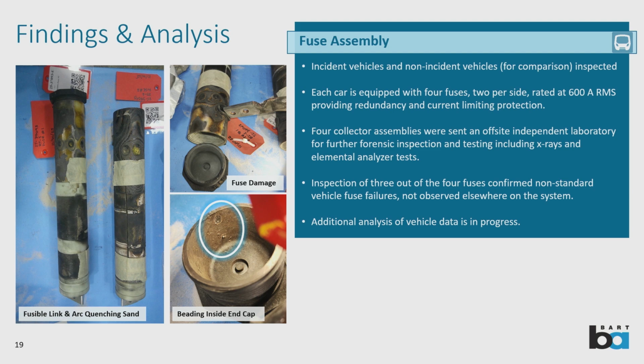There are other signs too, looking at the lug. The braid connects to the fuse, and that rectangular piece coming in at an angle with two holes also shows material loss, with a kink in it that isn't part of the design. That's another sign there was perhaps high energy arcing at that point.